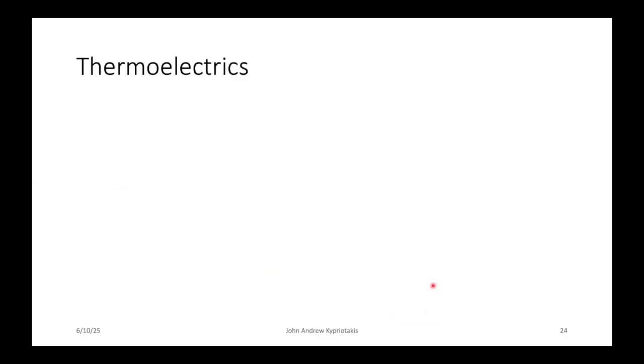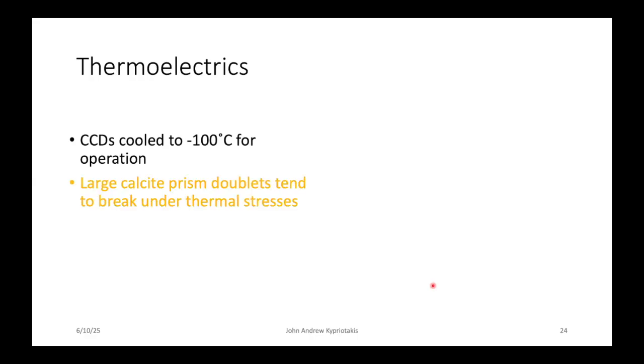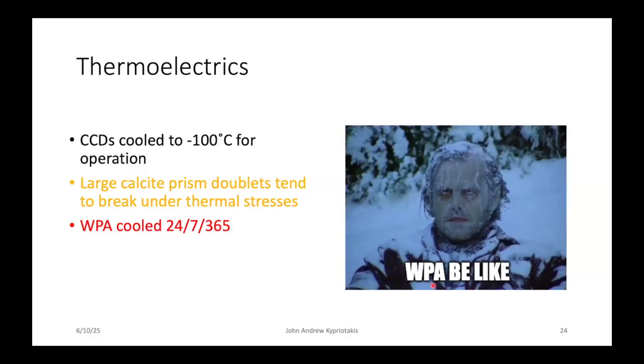Now, the reason that we actually need the triply fail-safe power supplies are thermoelectrics. Our CCDs are cooled to minus 100 degrees during operation, and that's standard pretty much in all astronomy to have CCDs cooled that low to reduce the dark current. But our large calcite prisms will break even under the very small thermal stresses of being heated and cooled at all times. So we had to take a measure to keep them cool at all times. So our Wollaston prisms are cooled 24/7 all year round in order to avoid them breaking.